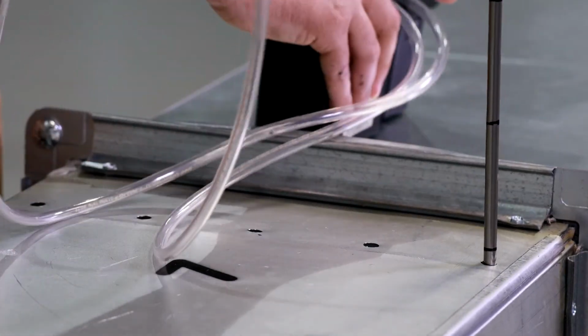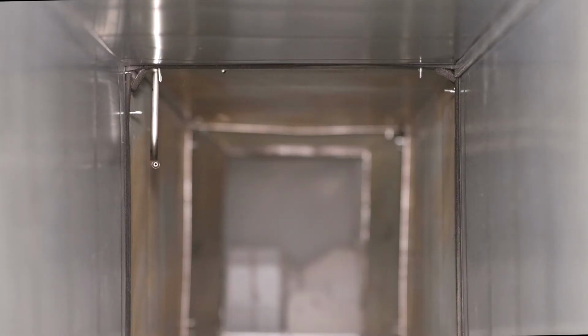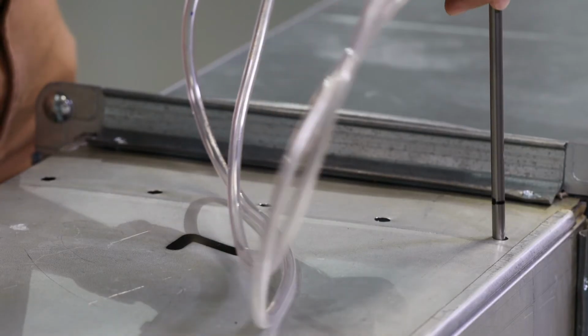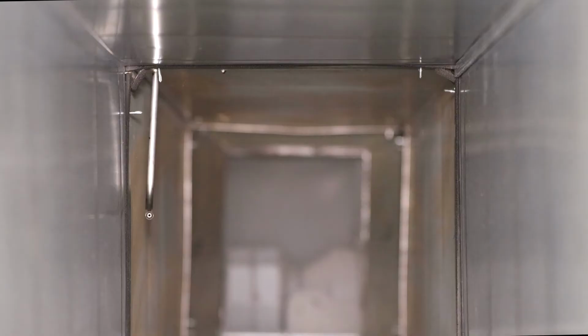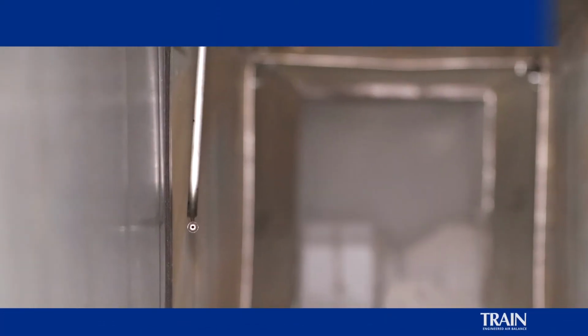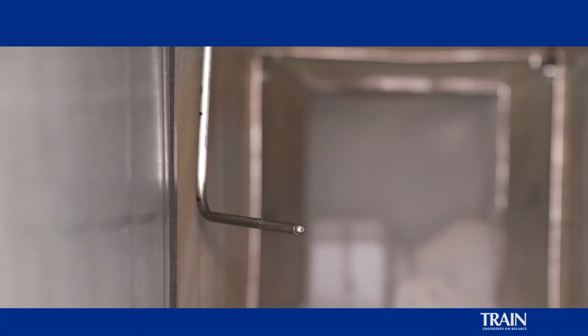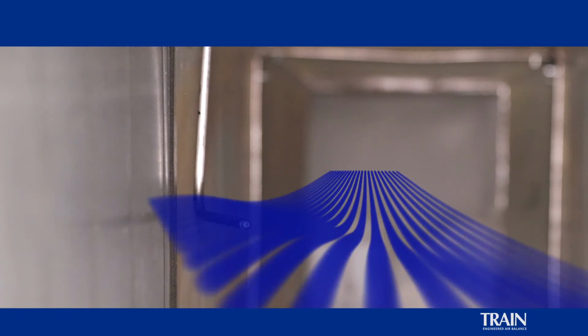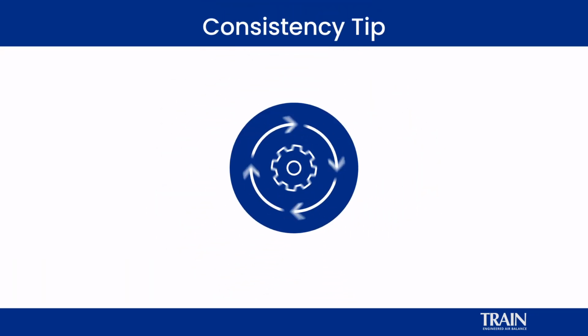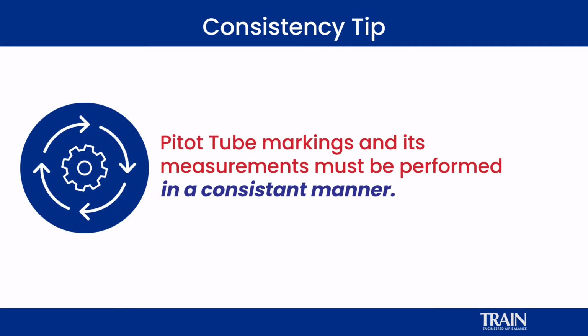Here we can visually demonstrate the location of the pitot tube inside of a duct when performing a pitot tube traverse. We can visually see that the pitot tube must be oriented into the airstream. It must be perpendicular to the airstream in a cross-sectional plane. We do not want to see the pitot tube at an incorrect angle, since that will produce erroneous readings and provide unacceptable data. It's also important that the pitot tube be gridded off and measurements taken in a consistent manner.